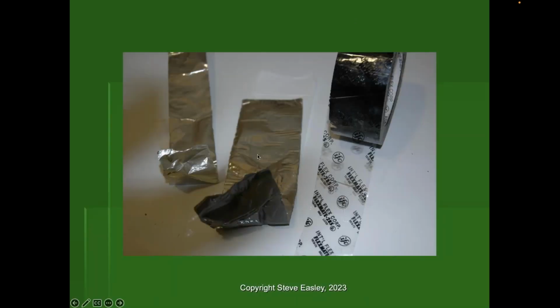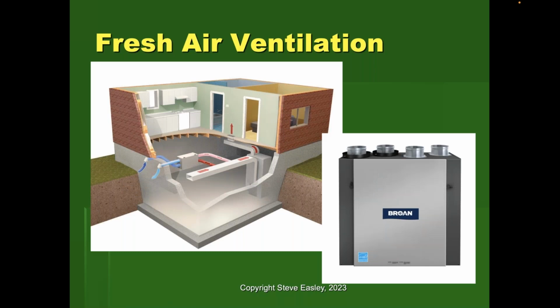Typically, the codes require that you use one of three types of duct tape, not the standard gray duct tape that we use to fix everything in the trunk of our car, right? That we keep for emergency use. But this is the UL 181B-FX tape. It has acrylic-based adhesive. This has butyl-based adhesive. This is a metal tape with acrylic-based adhesives as opposed to rubber-based adhesives, which dry out and cause problems.